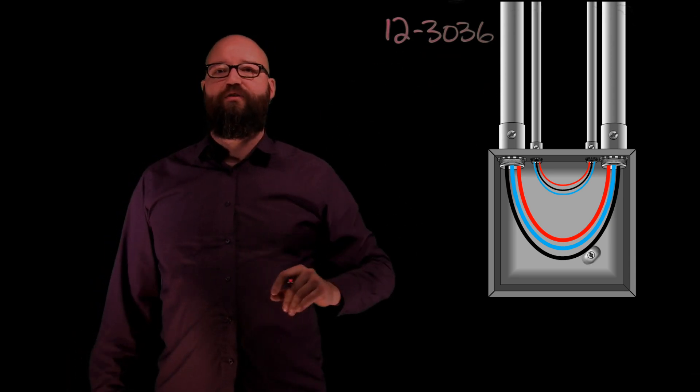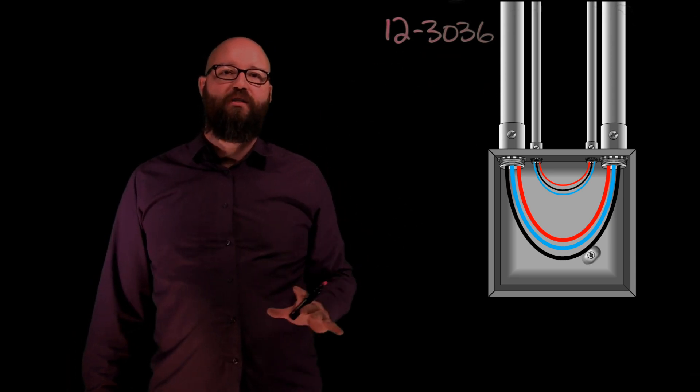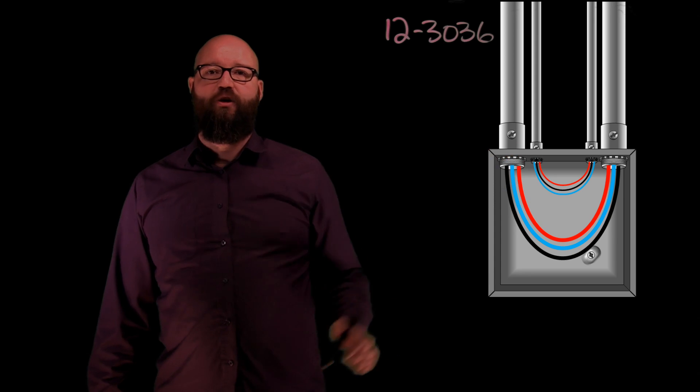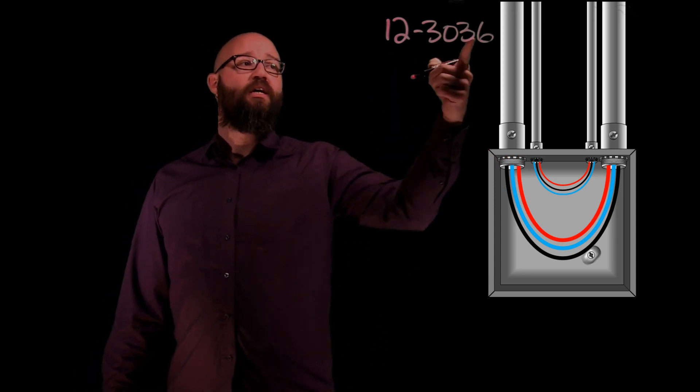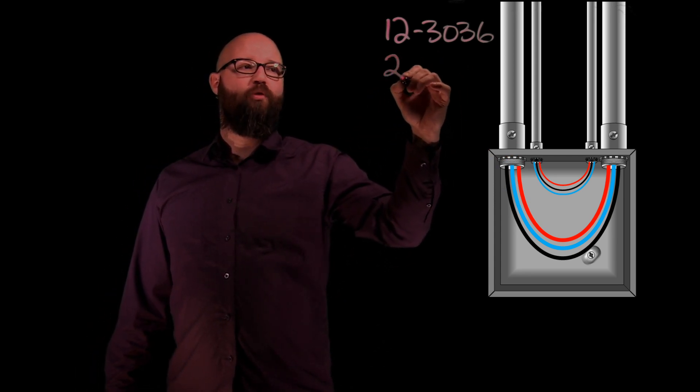12-3036 is where we take a look at pull boxes that contain conductors larger than a number four gauge conductor. So specifically what we're going to be looking at for sizing our U-pull junction box is 12-3036 sub rule two.